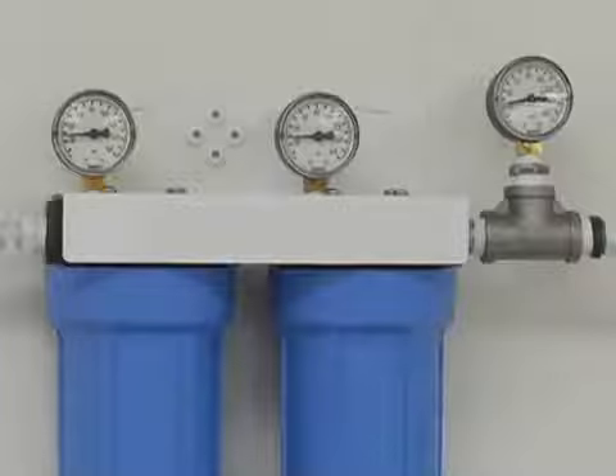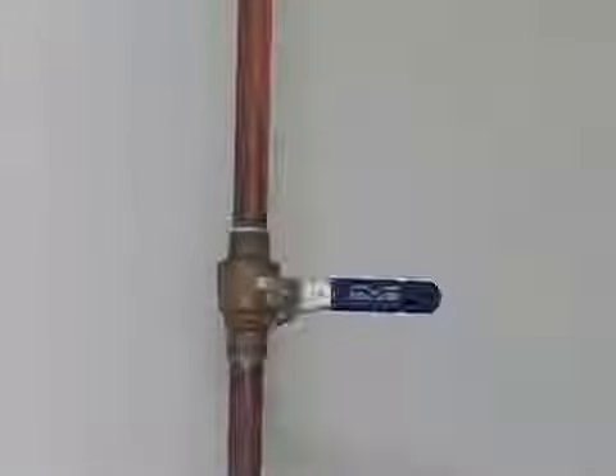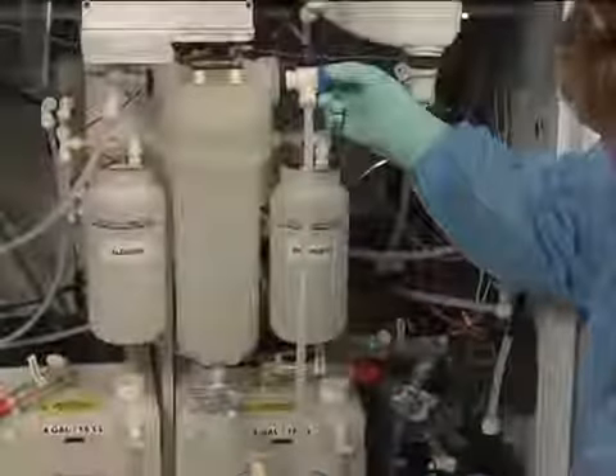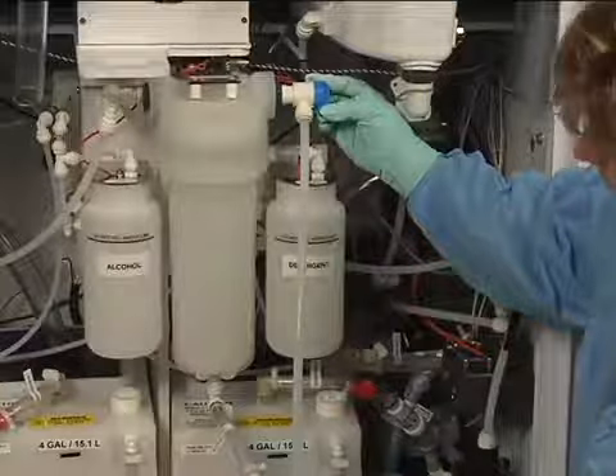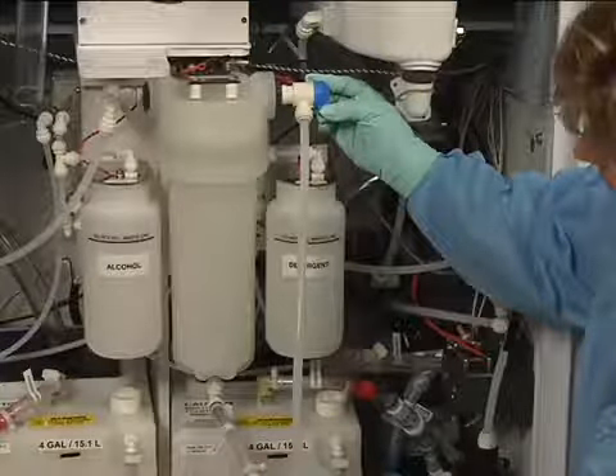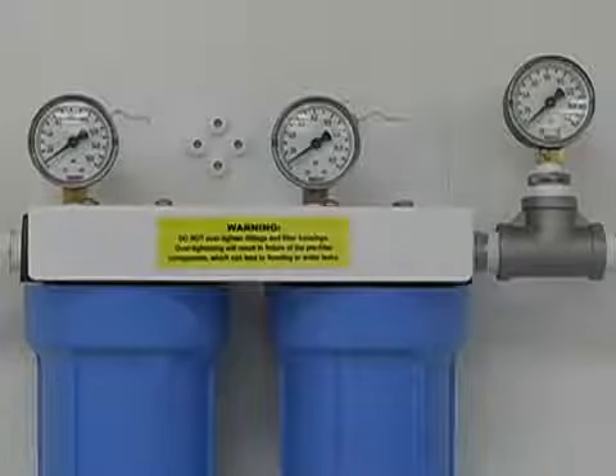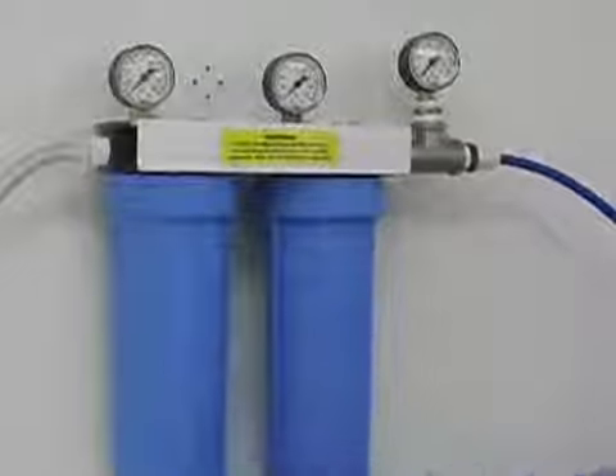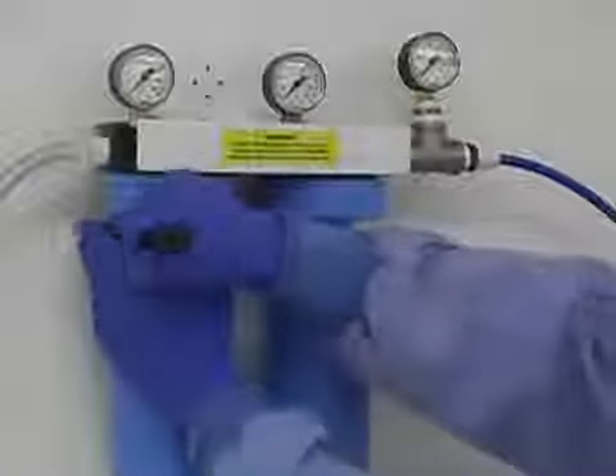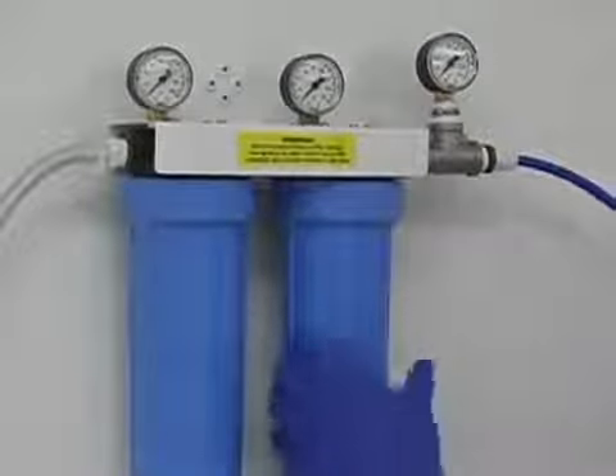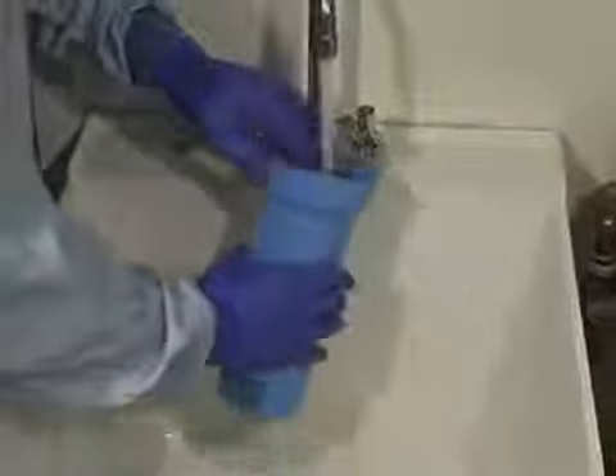To replace the pre-filtration filters on the wall, turn off the water supply to the system at the shutoff valve. Open the air bleed valve near the top of the 0.2 micron filter housing and release the pressure to facilitate removal of the individual housings. The gauges should read 0 psi. Place a container under the appropriate filter to catch excess water. Slowly loosen the filter housing with a filter wrench. Remove the filter, discard it, and any water in the housing. The two housings can be cleaned by washing and brushing with neutral pH low-foaming medical-grade detergent, rinsed, then dried with a lint-free cloth. Replace with a new filter of the correct size.